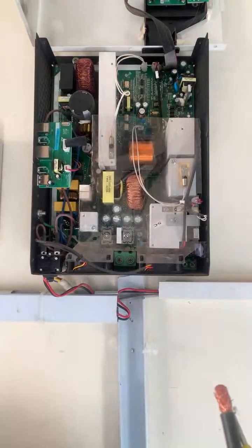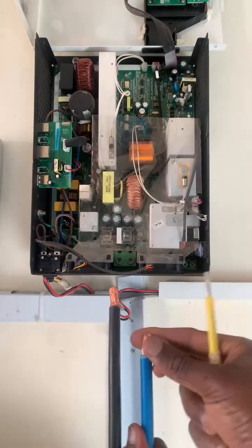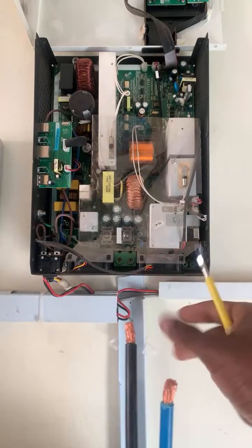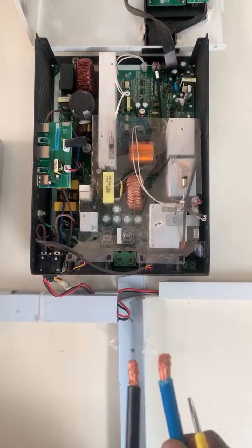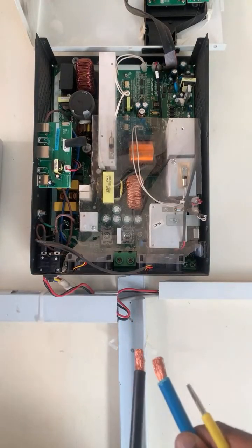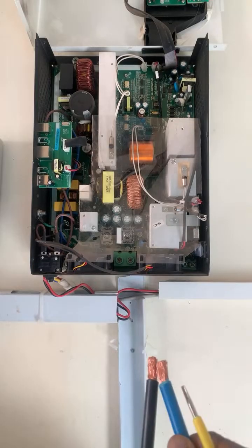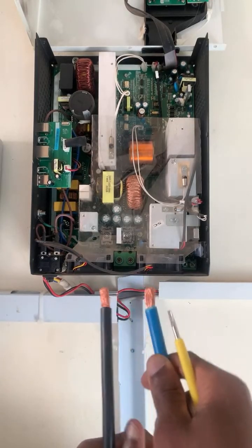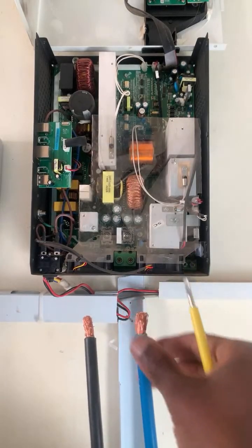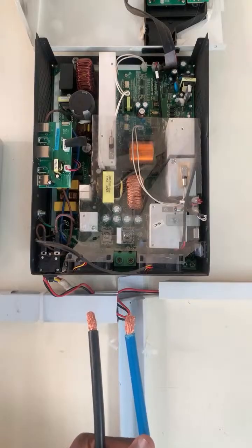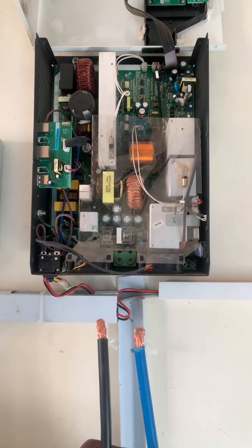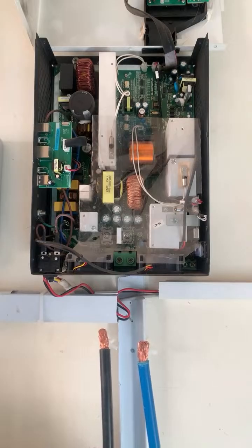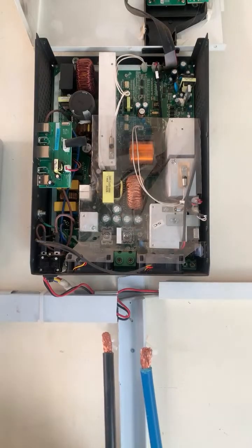So we have these two cables. Very important for you to note is that we will not connect these cables to the battery first, because in the process of connecting them to the inverter, you might short circuit them. If they're already connected to the battery, bringing these cables into contact will cause a problem. A short circuit is drawing very high currents from the battery within a very short period of time. Consequences: damaging the cells, especially for this type of battery.